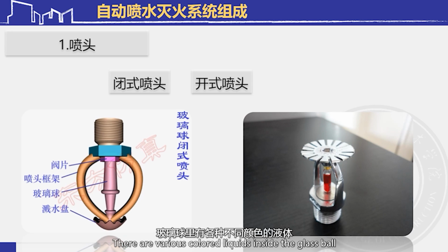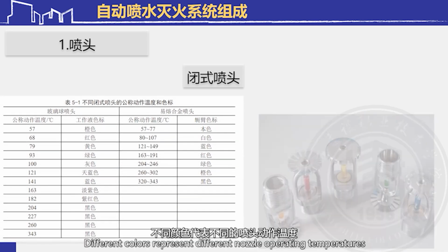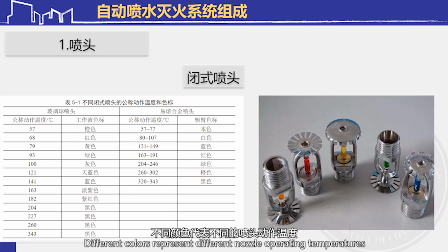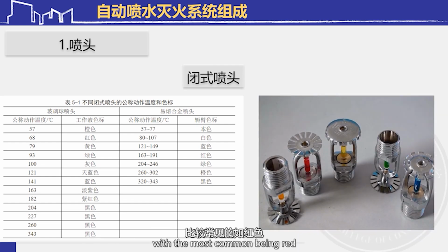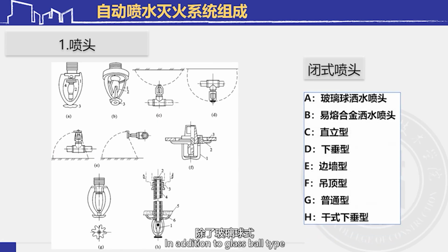There are various colored liquids inside the glass ball. Take a look at this set of tables. Different colors represent different nozzle operating temperatures, with the most common being red, which has an operating temperature of 68 degrees Celsius. Yellow at 79 degrees Celsius. Green at 93 degrees Celsius. In addition to glass ball type, it also has melting alloy component type.